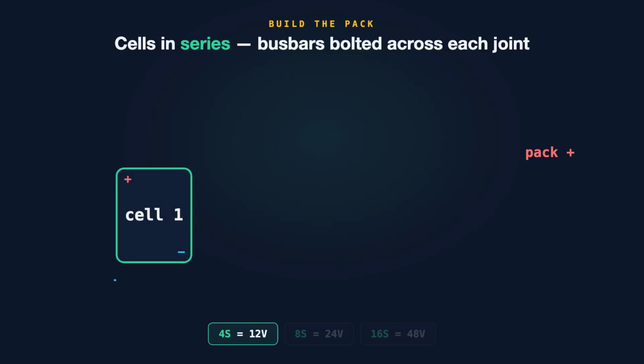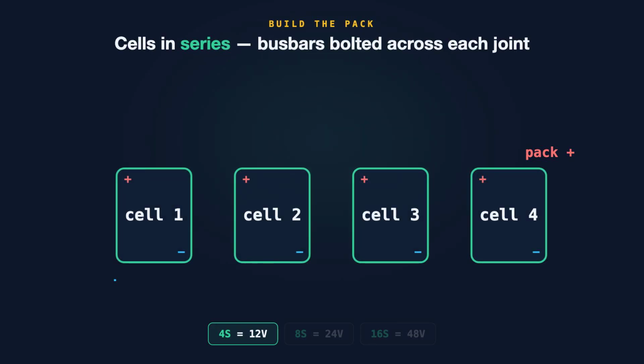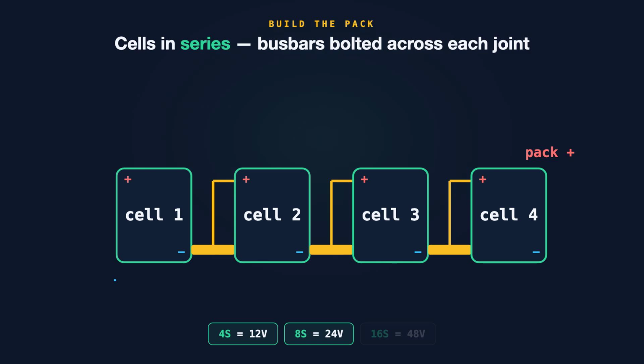Right, let's build the pack itself. Start with the cells. For a 12-volt pack, you wire 4 LiFePO4 cells in series. That's what 4S means, 4 cells in series. Want 24 volts? 8 cells. 48? 16. In series, the positive of one cell links to the negative of the next, with a solid bus bar bolted across each joint. Those bus bars carry the full pack current, so they have to be tight and clean. At the very bottom sits the pack negative, the whole string's minus. At the very top, the pack positive. Everything positive in the system ties back to that top.